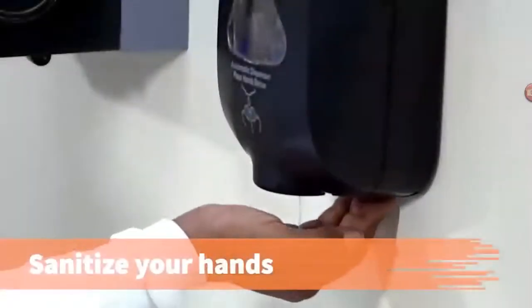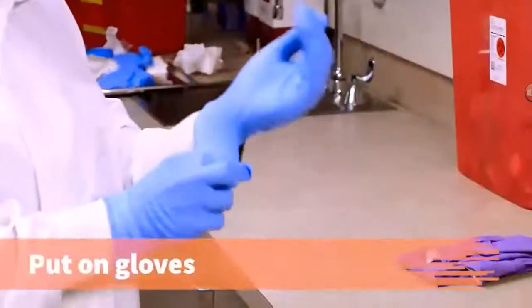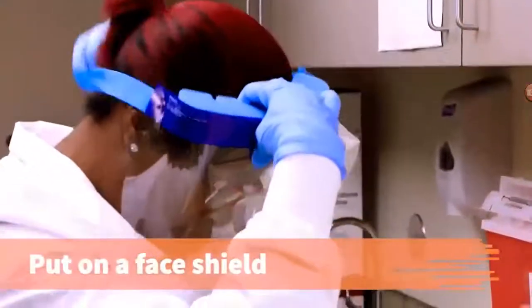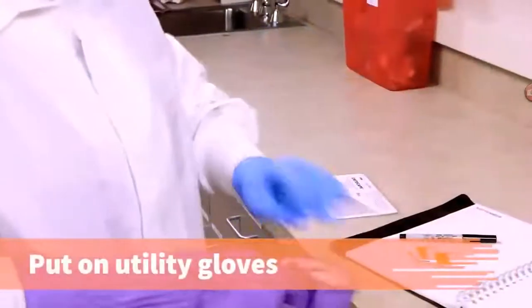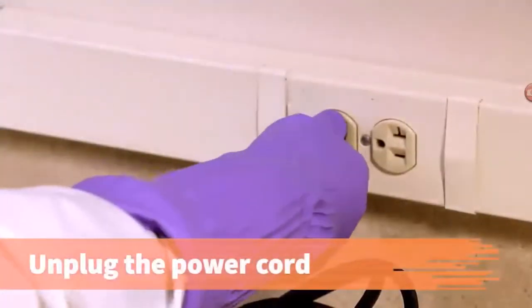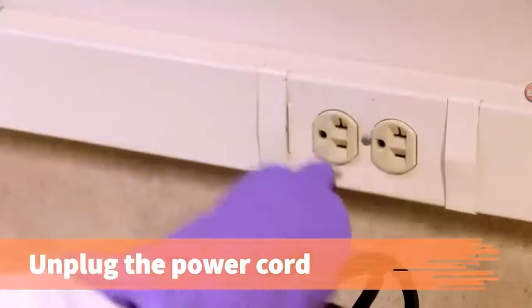First, wash your hands or use hand sanitizer. Put on a fluid impermeable lab coat, disposable gloves, and face shield. Then put on utility gloves over your disposable gloves. Always unplug the power cord before cleaning or servicing the centrifuge.